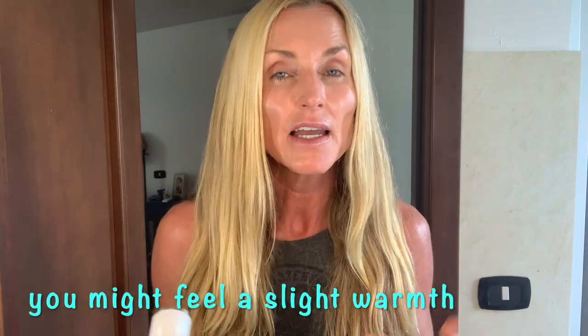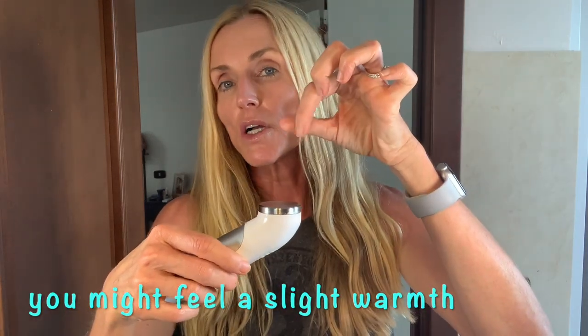Not feeling anything is normal with ultrasound — you don't feel it. However, if you put a couple of drops of water on the ultrasound head, it will start to bubble, so you can confirm it's actually working.